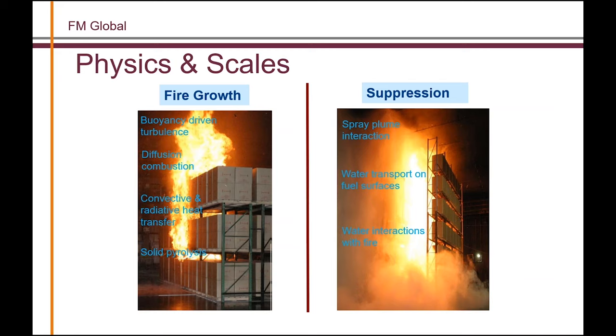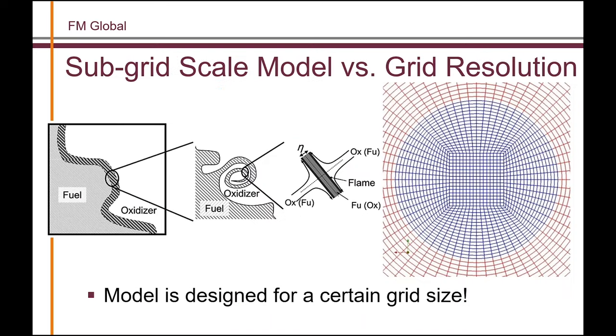Beyond the additional physics, there is another issue of scale. In industrial fire suppression, we're typically talking about tens of meters — a 50-foot warehouse with high storage. So the computational domain is large. On the other end, the small-scale physics and geometry can be at the millimeter level — heat transfer near the wall, droplets, detailed rack geometry — requiring much smaller resolution. There is a big scale separation from large scale to small scale. The larger the scale separation, the larger the total mesh size needed and the higher the computational cost.